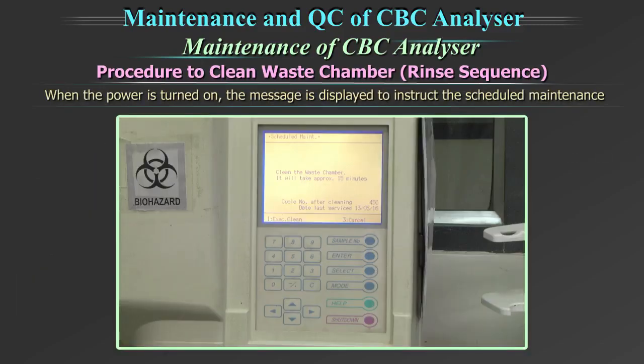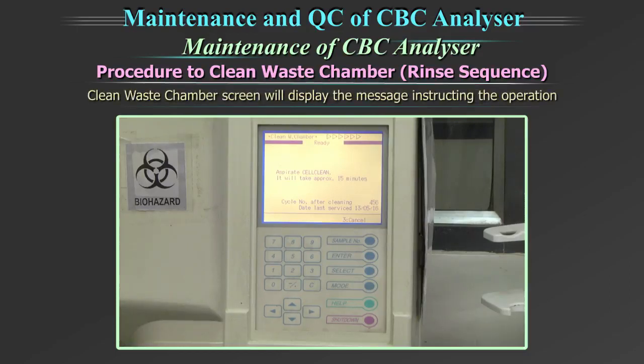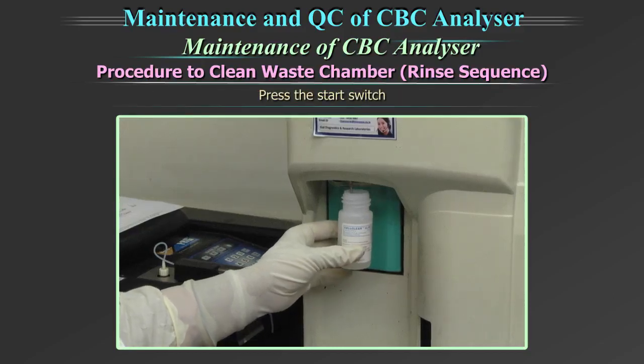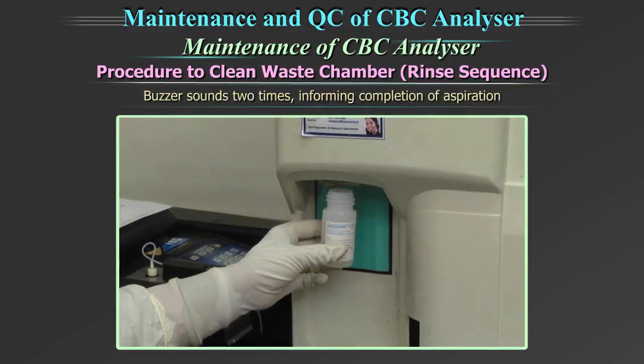When the power is turned on, the message is displayed automatically to instruct the scheduled maintenance on the due date. Select 'Execute Clean' on the scheduled maintenance message screen. The clean waste chamber screen will display the message instructing the operation. Set the cleaning solution to the sample probe and press the start switch. While 'Aspirating' is displayed on the screen, keep holding the cleaning solution in the same position.